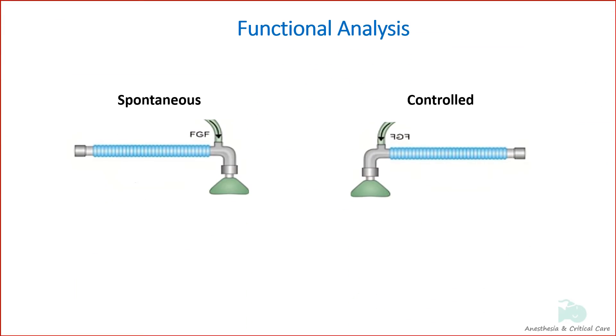For spontaneous ventilation, the expiratory limb is open to the atmosphere. Controlled ventilation can be performed by intermittently occluding the expiratory limb and allowing the fresh gas to inflate the lungs.